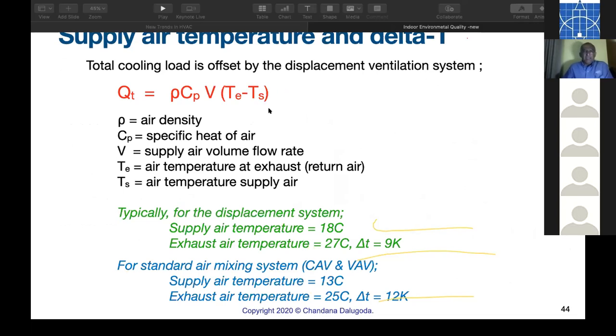Total cooling capacity offset by displacement volume can be calculated like this. Now, I have given an example here. The displacement system supplies air at 18 degrees and exhausts at 27, a 9K delta T. For constant volume and variable air volume mixing systems, we have 12 to 13 degrees supply air and exhaust at 25, with 12K. Now we have a bit of a worry. In a mixing system, we have a 12K delta T, and in a displacement system, if you use it in Sri Lanka, delta T is 9K. Whether we could get a good cooling load, let's see.